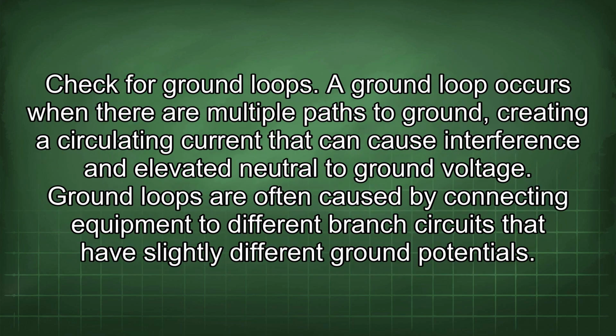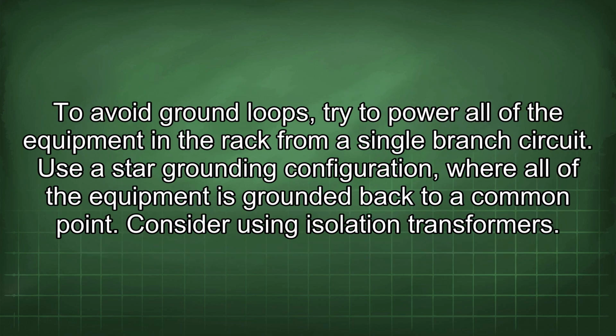Check for ground loops. A ground loop occurs when there are multiple paths to ground, creating a circulating current that can cause interference and elevated neutral to ground voltage. Ground loops are often caused by connecting equipment to different branch circuits that have slightly different ground potentials. To avoid ground loops, try to power all of the equipment in the rack from a single branch circuit. Use a star grounding configuration, where all of the equipment is grounded back to a common point.